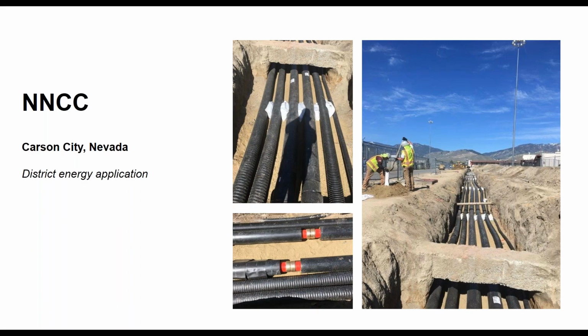The picture on the left shows the mechanical connection used, a sleeve cold expansion technology. After we put the fitting in place we insulate it; they use a slightly different insulation strategy on this system than in one of the earlier pictures - we have a couple options to offer. They were able to meet the state's needs for a quick in-and-out project that would have taken a year with steel, but we did it in weeks with pre-insulated PEX, while also working around weather schedules.